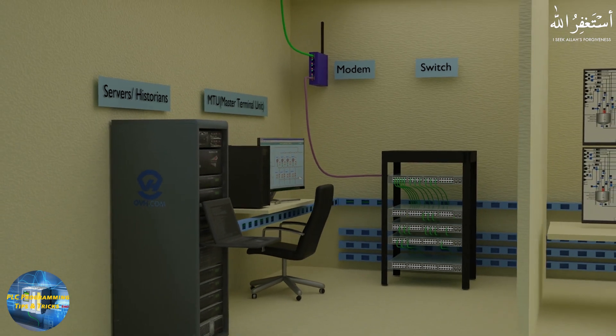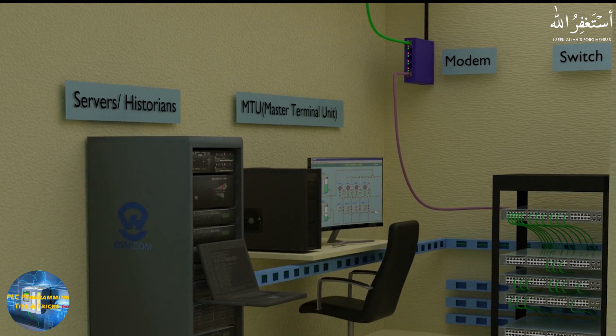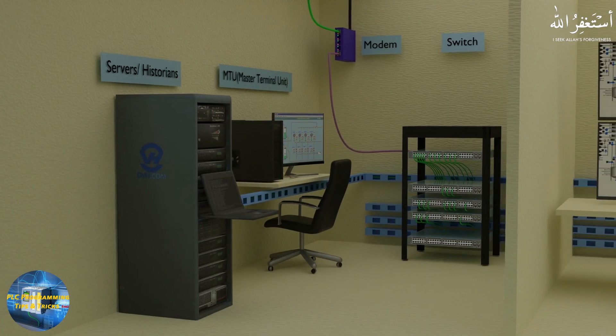The next component is the MTU — Master Terminal Unit — which is the brain of the SCADA system. The SCADA control software runs on this system. The MTU receives data from field devices and remote locations, analyzes it, saves it, and takes critical control decisions to keep the process running. MTU units send this data to the server historians, which continuously log the data and keep it safe and available. This data is essential for monitoring and analyzing operations and can also predict upcoming breakdowns in the future.